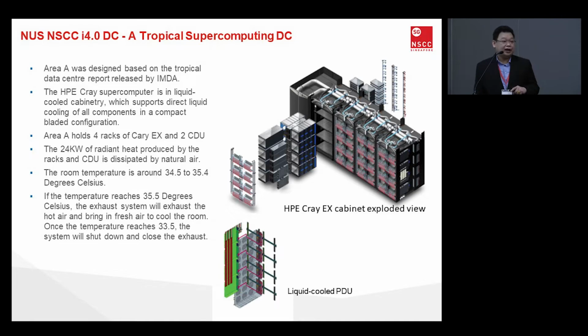Of course, the other issue we have is humidity here. In Singapore, it's humid, okay? So the moment we open up, we're pulling in humidity also. But however, we don't have much of an issue because firstly, the room is hot. Let's talk about the room humidity on the average. The room humidity on normal operating average is about 40% humidity. So that's relatively quite good. It's already a computer room humidity already. So even if we pull in humid air from outside when we do the heat exchange, it goes up at a maximum of about 20. So you're looking at about 60 humidity, which is still good at the current moment.